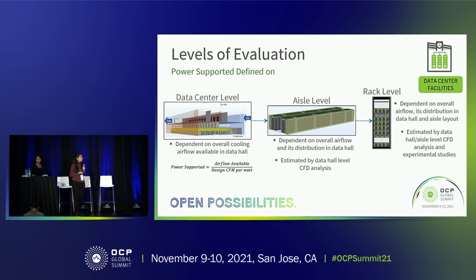So in this case, we estimated the aisle level airflow using DC-CFD simulations, and we are able to come up with a number that is the IT airflow that we are able to support in all of our aisles. Moving down one more level, which is the rack level airflow, this is where it starts getting even more interesting and nuanced. So now we have the total airflow that is available, how it is distributed throughout the data hall, and then also some localized phenomena when we see some high CFM racks or high airflow racks, and the effects of pressurization. And this is where we now have to come up with constraints and try to evaluate what are the limits we are able to support for these high airflow racks.